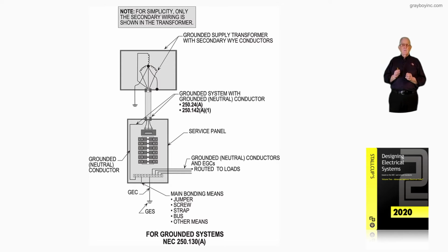250.102C1 based upon the ungrounded phase conductors, as we've mentioned a number of times through this Chapter 16, if you've been reviewing the entire chapter. But 250.24A and 250.142A1 deals with supply side, and we know this is supply side grounding we're talking about here because the transformer conductors that are tapped, transformer and secondary conductors routed to the main through the conduit. There's no overcurrent device ahead of them, so that is supply.